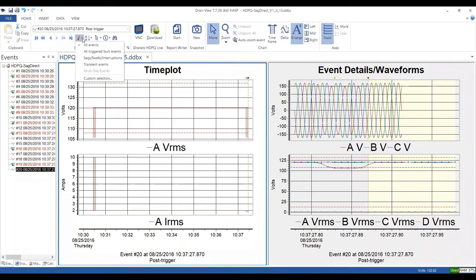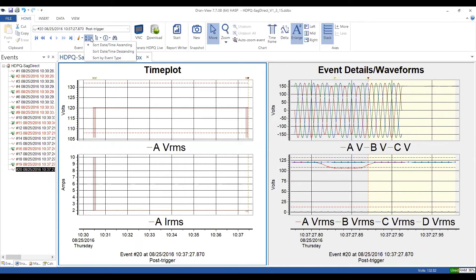Over here you have the event subset, which is an event filter. You can view events by type: all events, all triggered events, sag and swell and interruptions — which shows only those RMS-type events — or transient events only. Triggered events would exclude journal events, and SAG/swell/interruption filtering would exclude snapshots and transients. You also have the ability to sort ascending or descending or by event type.